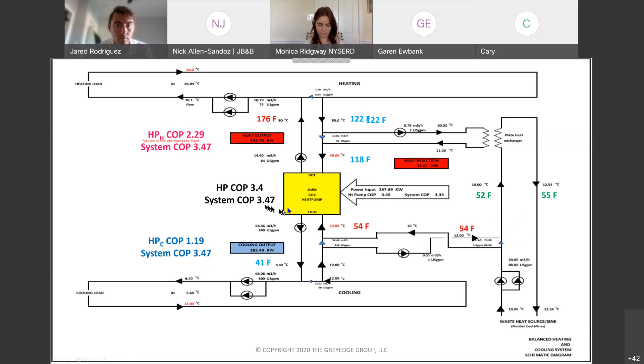Another piece of equipment I wanted to show you is what one of these skid-mounted CO2 heat pumps looks like. What I want to bring to your attention is that when we're getting into these high temperatures, look at the COPs we're able to maintain. Heretofore, this is unheard of. Now, the CO2 doesn't cool as well, in the sense that its COPs are a little lower on that side, but this is a primary heating source. So if you've got a heating dominant system, this might be one of the things you want to look at.